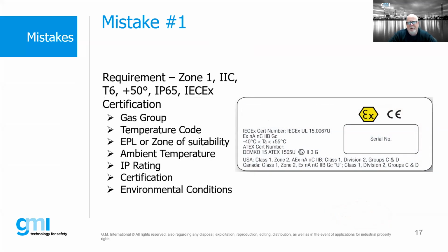Now here's another one. Again, a similar application. In this case, we actually have quite a few issues. Ex nA and nC is the protection concept. Based upon the EPL of Gc, this is telling us that this product is only suitable for a Zone 2 environment. The requirement for the project is Zone 1. The other thing we see here is that when we look at their certificate, we see a U at the end of it. We're going to talk about this in just a little bit, but when we see a U at the end of a certificate, that means it's a component. And that means that we cannot install a component into a hazardous area without further assessment.